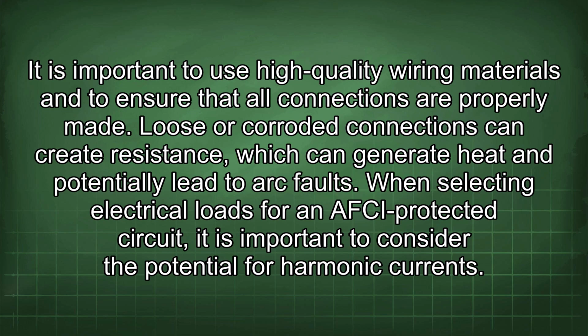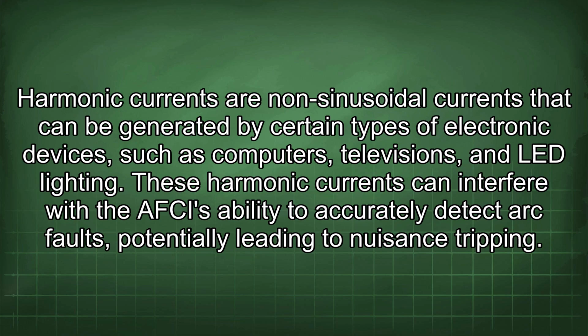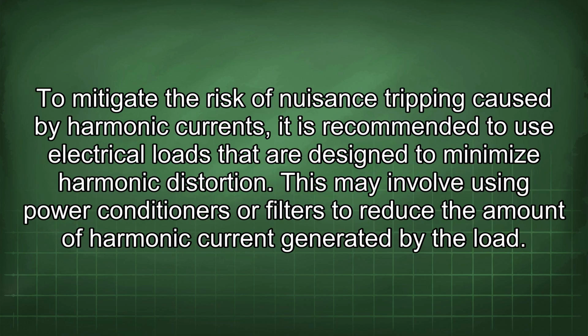When selecting electrical loads for an AFCI-protected circuit, it is important to consider the potential for harmonic currents. Harmonic currents are non-sinusoidal currents that can be generated by certain types of electronic devices such as computers, televisions, and LED lighting. These harmonic currents can interfere with the AFCI's ability to accurately detect arc faults, potentially leading to nuisance tripping. To mitigate the risk of nuisance tripping caused by harmonic currents, it is recommended to use electrical loads that are designed to minimize harmonic distortion. This may involve using power conditioners or filters to reduce the amount of harmonic current generated by the load.